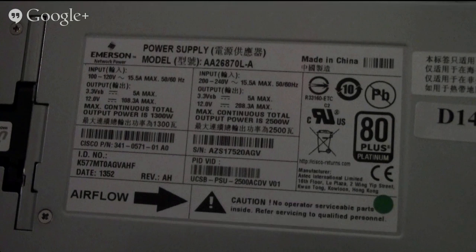So we might get to a point after maybe, depending on blade configuration, 4 to 6 blades, where maybe the 7th blade wouldn't be allowed to be powered up because we wouldn't have enough power to be able to power that blade and keep redundancy. So that's something that we definitely had to do a lot of work on, and that's something that people need to be aware of, that when you do run at low line voltages, you could run into some limitations on the number of blades that will actually power up.